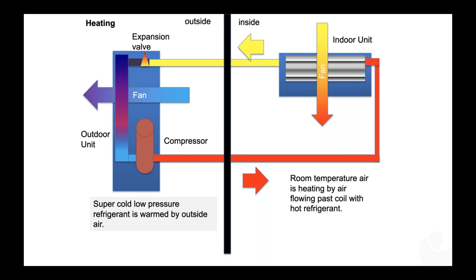And it's typically cheaper to use a heat pump than to burn number two heating oil until you get down to about 0 degrees, where you hit the balance point. But even at that point, at negative 5 degrees or negative 10 degrees, you're saving pennies. And so over the course of the entire season, the difference between using a heat pump above and below 0 degrees versus your conventional heating system might amount to a grand total of $5. So generally speaking, the recommendation is to leverage your heat pump to the maximum extent possible throughout the entire season. And know that if you size and select equipment that's large enough to accommodate your design load for your house, you can displace 100% of your heating load without any augmenting backup heat source.